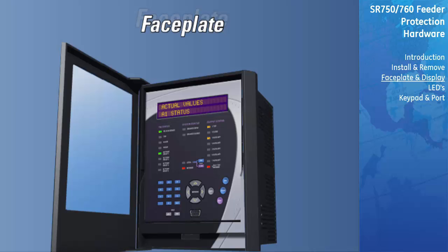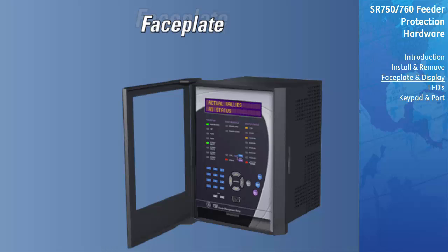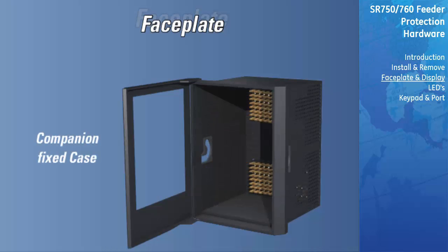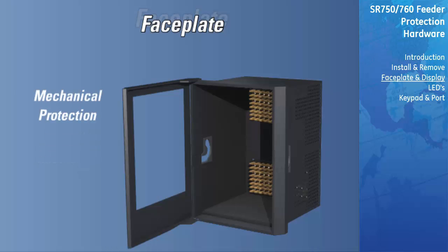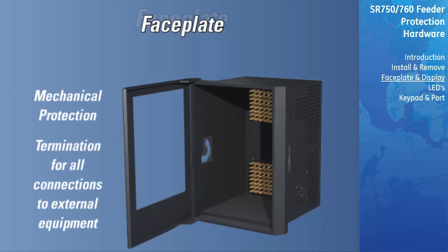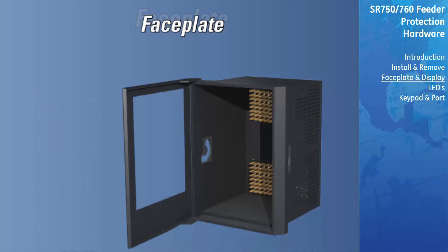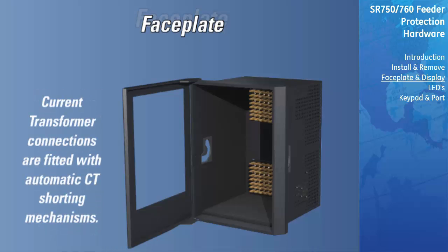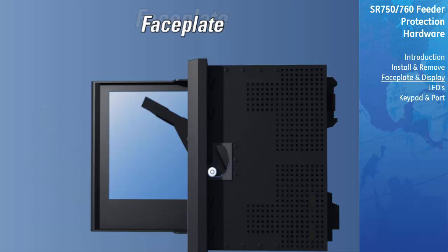The relay is packaged in the standard Multilin SR series configuration of a draw-out unit and companion fixed case. The case provides both mechanical protection and is the termination for all connections to external equipment. Current transformer connections within the case are fitted with automatic CT shorting mechanisms. The unit is held in the case by pins on the locking handle, which cannot be fully lowered to the locked position until all electrical connections are fully mated.